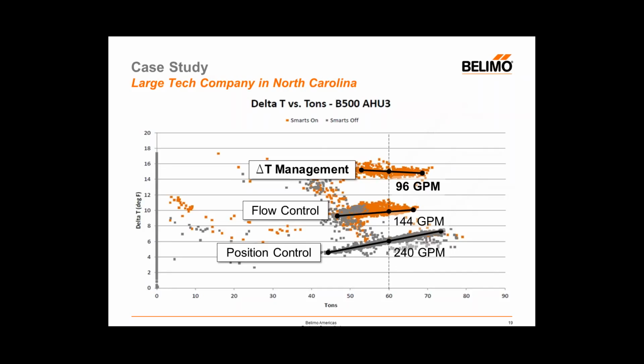So the one last thing I want to remind you about before we close out and go to the question and answer session today is that the energy valve is not sort of magical. It doesn't make your coil behave better than its design. What it allows you to do is operate your coil at its design. What we see most places is that we have 16-degree coils in place that are operating at 8, 9, 10 degrees F, and then I have a 16-degree chiller plant that's running at 8, 9, 10 degrees F.